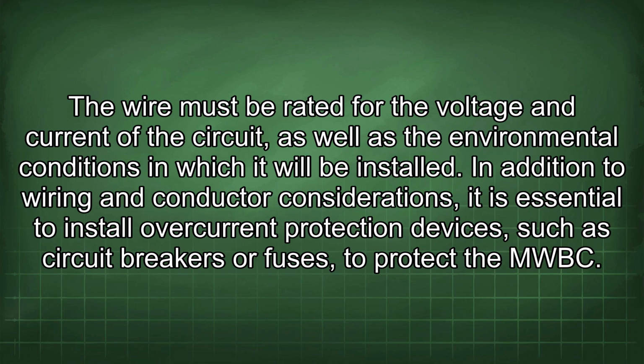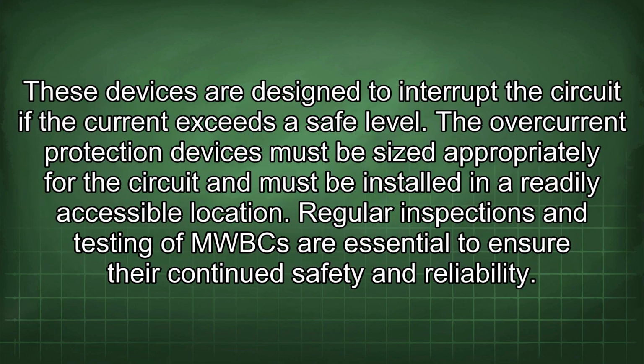In addition to wiring and conductor considerations, it is essential to install overcurrent protection devices, such as circuit breakers or fuses, to protect the MWBC. These devices are designed to interrupt the circuit if the current exceeds a safe level. The overcurrent protection devices must be sized appropriately for the circuit and must be installed in a readily accessible location.